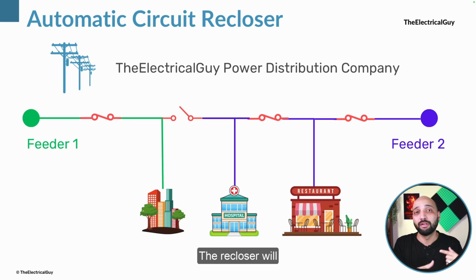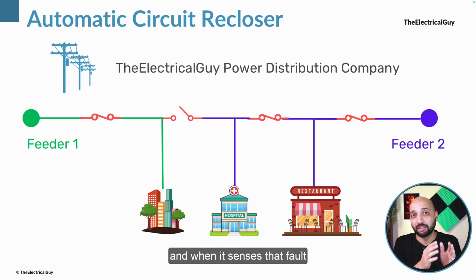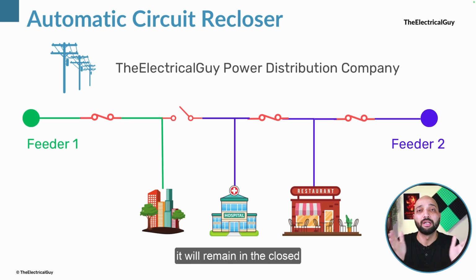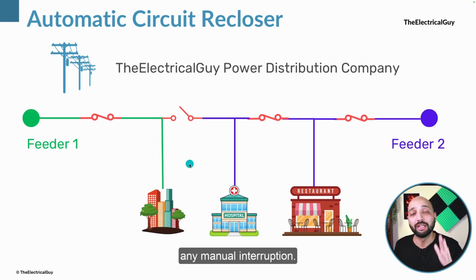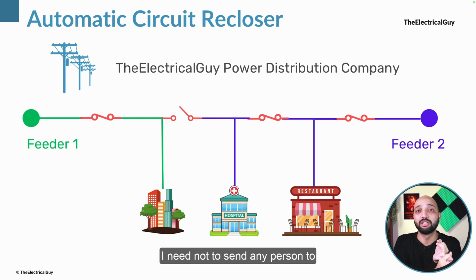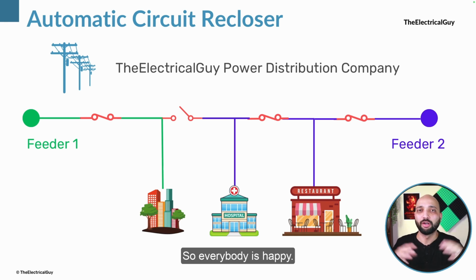The recloser will do its sequence, and when it senses that the fault is no more in the system, it will remain in the closed condition and my supply continuity is back without any manual intervention. I need not send any engineer there to check. I need not send any person to manually close the breaker. It is closed automatically. The supply continuity is maintained. My customers are happy. My company is happy because I'm giving a continuous supply to my customers. So everybody is happy. And that is the function, that is the importance of the recloser in the distribution network.